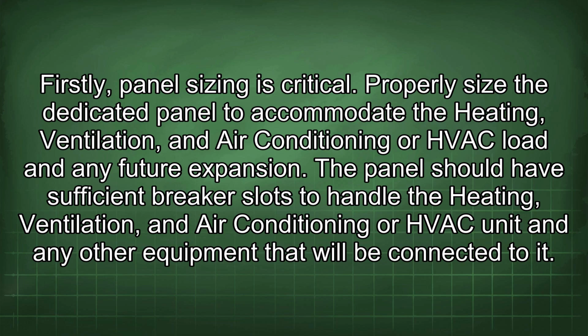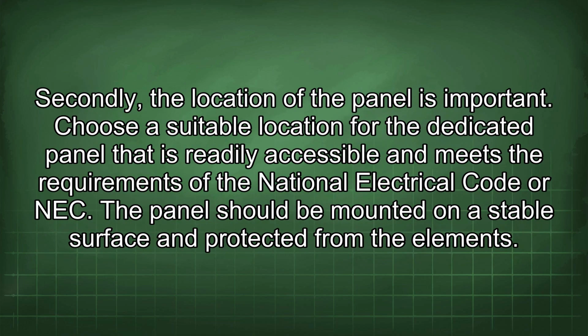Firstly, panel sizing is critical. Properly size the dedicated panel to accommodate the heating, ventilation, and air conditioning, or HVAC, load and any future expansion. The panel should have sufficient breaker slots to handle the HVAC unit and any other equipment that will be connected to it. Secondly, the location of the panel is important. Choose a suitable location for the dedicated panel that is readily accessible and meets the requirements of the National Electrical Code, or NEC. The panel should be mounted on a stable surface and protected from the elements.